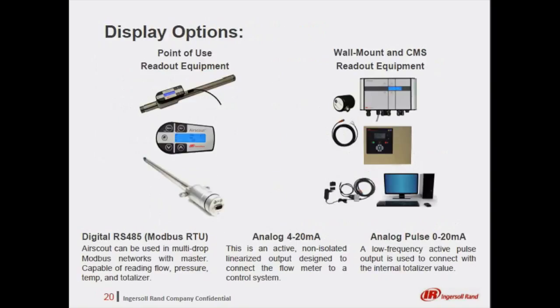When developing recommendations to a customer for flow meter installation, it's important to consider how and where the data is going to be viewed. The point-of-use display and data loggers, as well as the wall-mount terminal, all display current conditions, but data analysis capability is only available on the Airscout Studio.